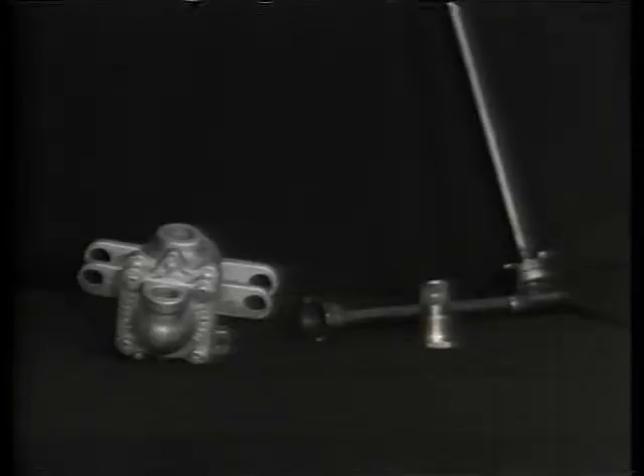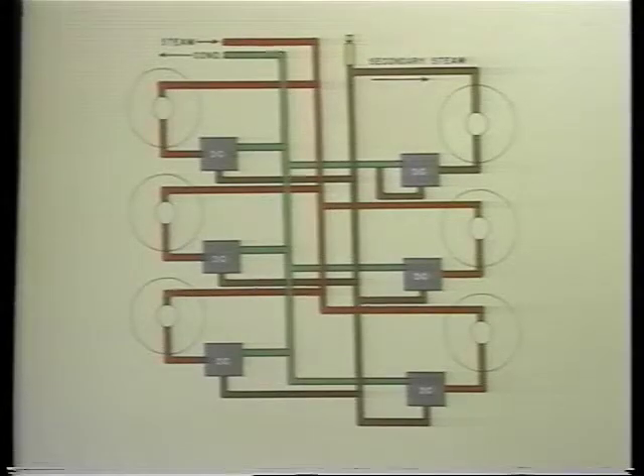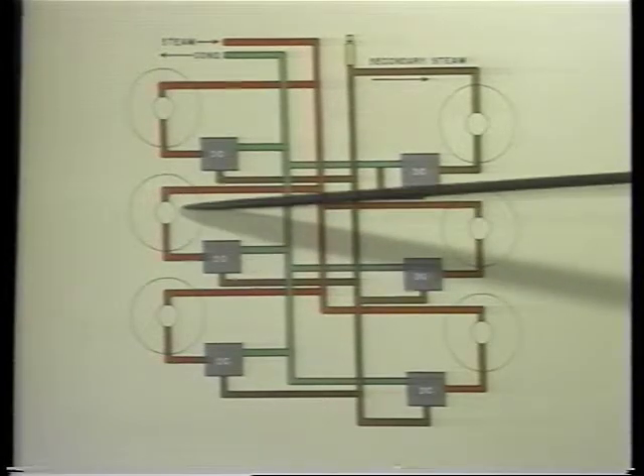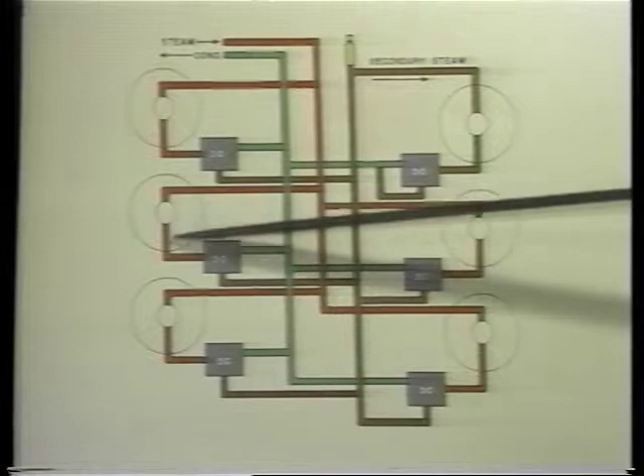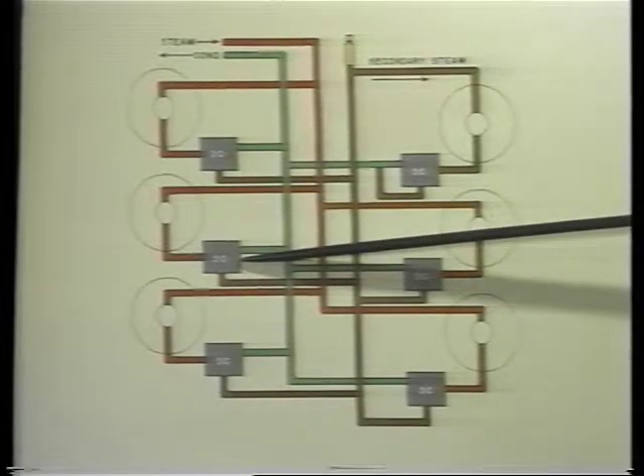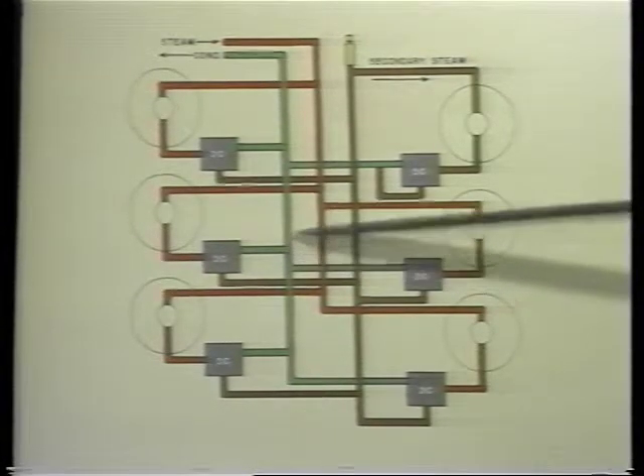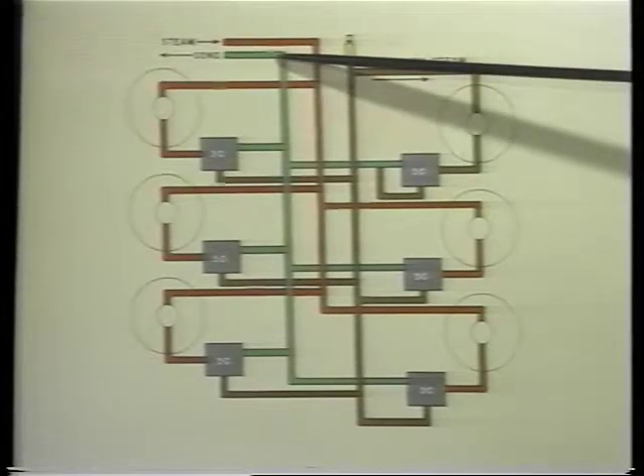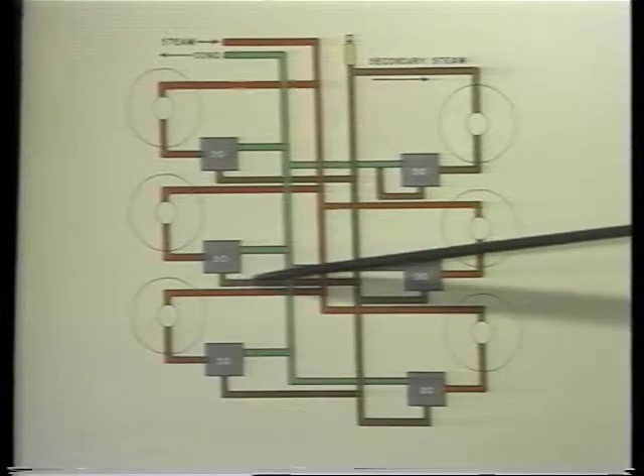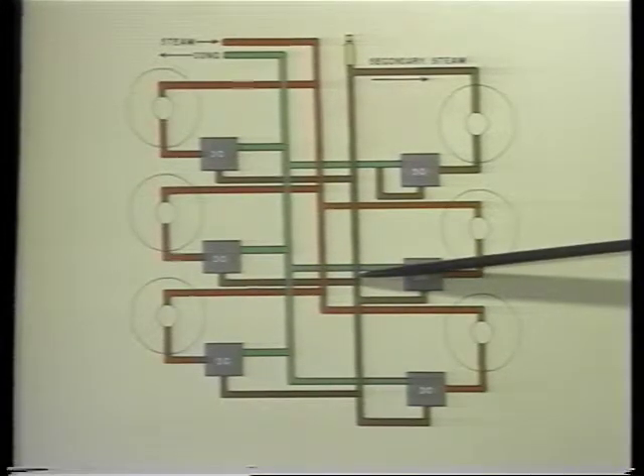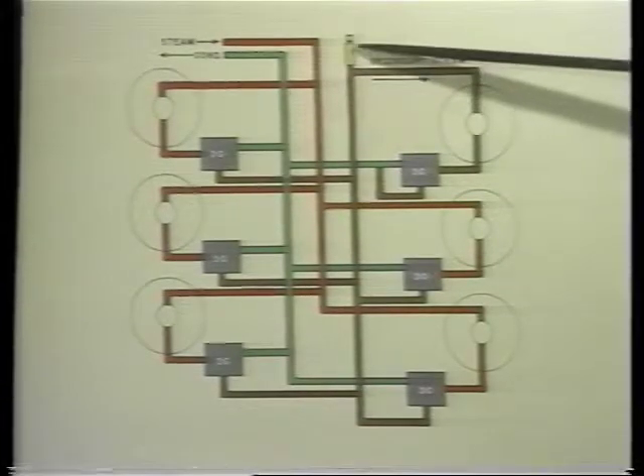The major components of the Heat-Tech system are rotary siphons, rotary joints, differential controllers, and air eliminators. Condensate, air, and a small percentage of blow-through steam enter the siphon pickup. This biphased mixture flows through the siphon out of the rotary joint to the differential controller. After this mixture enters the differential controller, the vapors, air and steam, are separated from the condensate. The condensate is discharged through the orifice into the condensate return line. The vapors flow into the secondary steam header, held at pressures slightly lower than supply steam pressure. Then, the thermostatic air vent removes all the non-condensable gases from the steam.